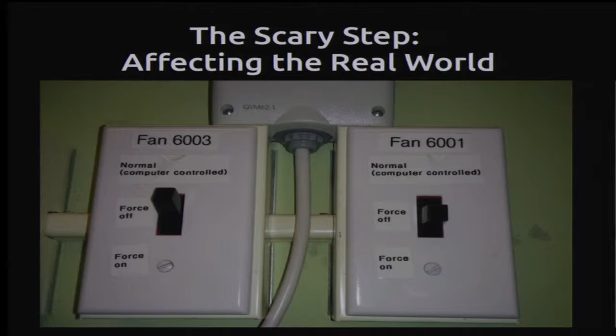This is a clickable interface, and what you can see there is two rules combined together in an OR fashion. So if the amperage of another fan is less than 7 amps, assume the fan has failed. Or if the temperature is over a certain threshold, turn another fan on.